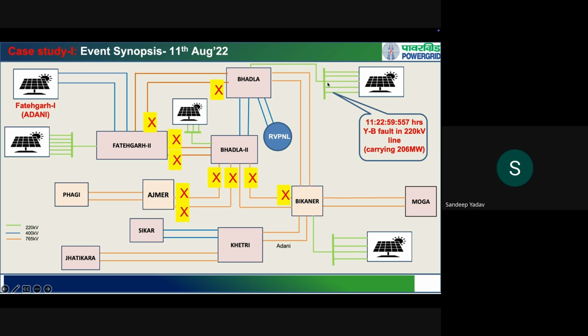So let's take an example of a Y to B fault, a phase-to-phase fault, on one of the 220 kV transmission lines directly feeding, which is connected to one of the solar generators. So a 300 megawatt solar generator is connected to the point of interconnection at the 220 kV bus of the power grid, and there is a phase-to-phase fault in that 220 kV transmission line.